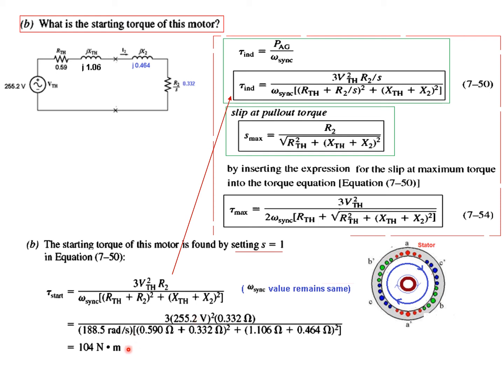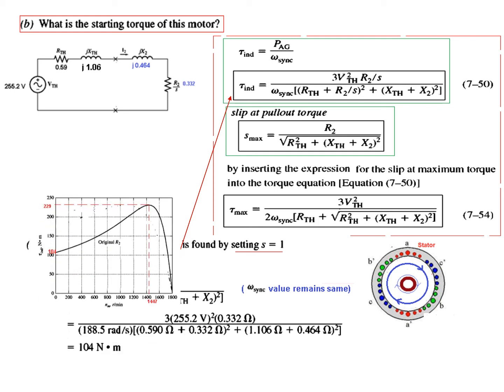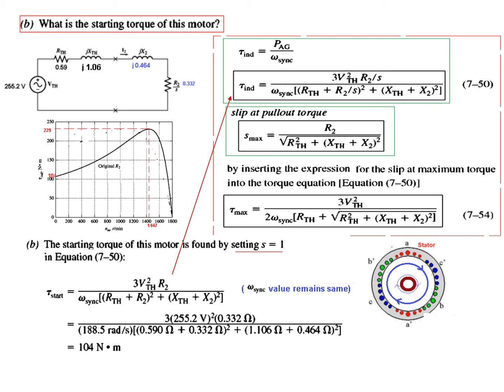This is the equation. Plugging in all the values, the starting torque will be 104 newton-meters. We go back to the graph to see this concept. The torque-speed curve starts at this point, which is 104 newton-meters when the speed is zero—that means the rotor is not moving.